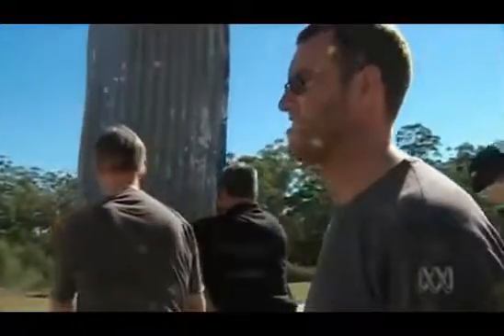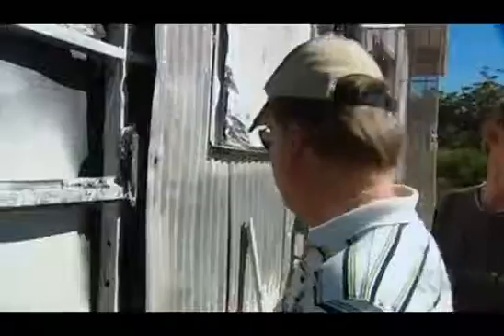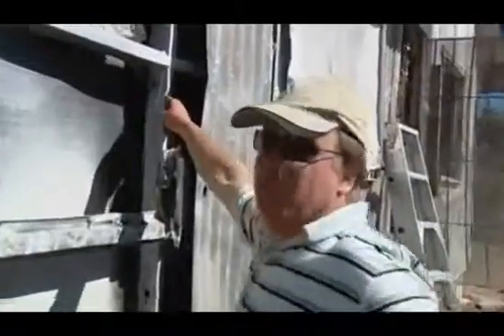There you go, there's the answer. Yeah. Melted glass insulation. The failure of the insulation may have affected the steel frame. That's a local buckle in the steelwork. When it got very hot, it got up to about 1000 degrees C. That would have to be replaced.